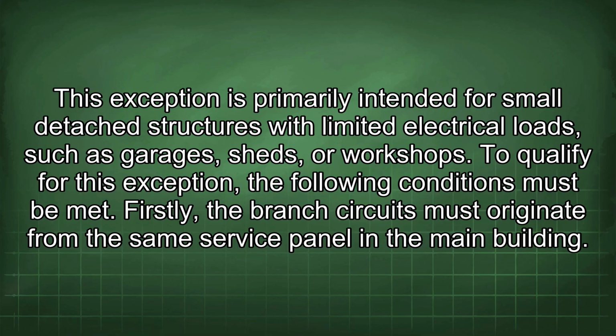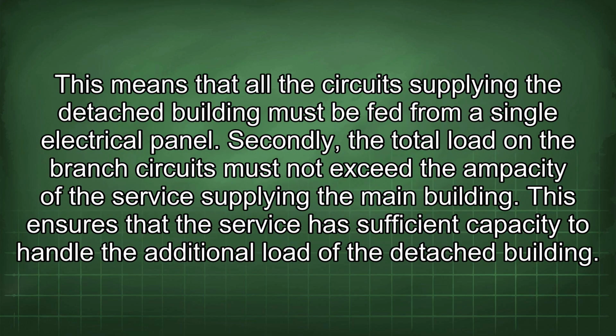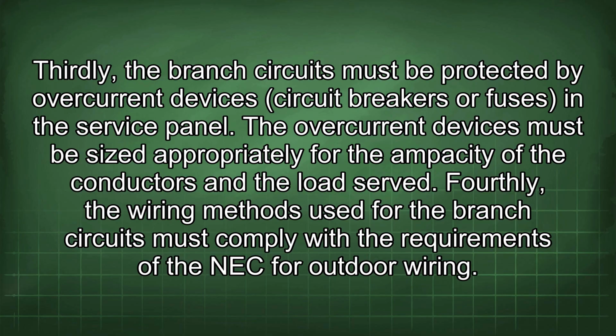Firstly, the branch circuits must originate from the same service panel in the main building. This means that all the circuits supplying the detached building must be fed from a single electrical panel. Secondly, the total load in the branch circuit must not exceed the ampacity of the service supplying the main building. This ensures that the service has sufficient capacity to handle the additional load of the detached building. Thirdly, the branch circuits must be protected by overcurrent devices, circuit breakers, or fuses in the service panel. The overcurrent devices must be sized appropriately for the ampacity of the conductors and the load served.